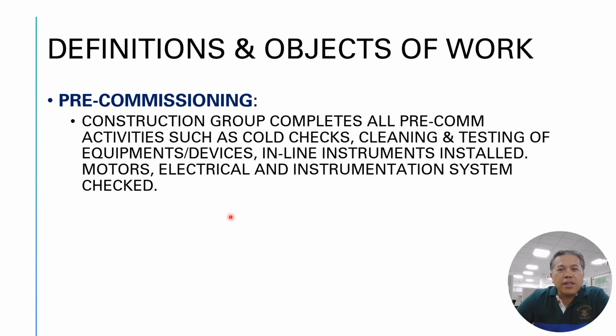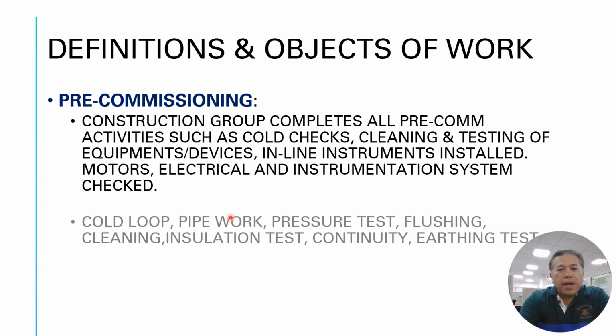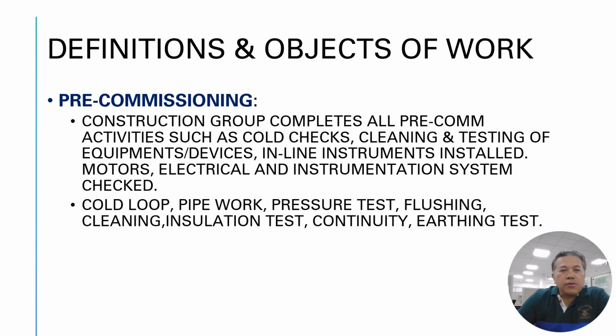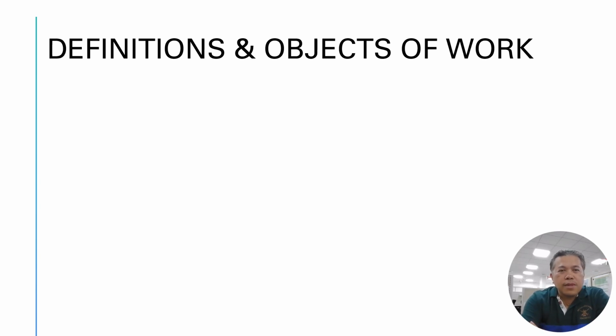Also, the inline instruments installed, that is related piping, so motors, electrical, and instrumentation systems need to be checked. You also need to complete the cold loop pipe work, pressure testing, hydro testing, flushing, cleaning, insulation test, continuity, and earthing test. That is the pre-commissioning work, definition, and objectives of the activities.